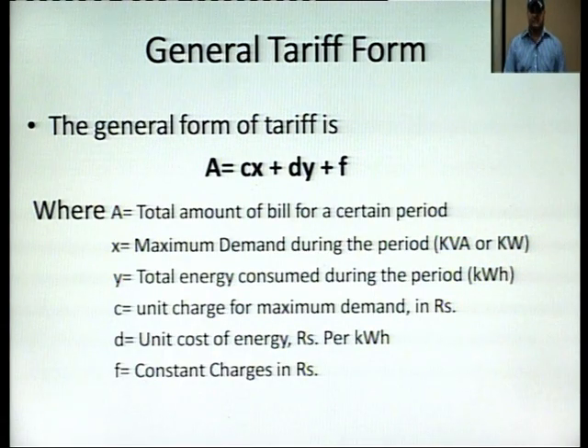Y is the total energy consumed during the period, in kilowatt hours. C is the unit charge for the maximum demand in rupees - so many rupees per kilowatt or per kVA. D is the unit cost of energy, in rupees per kilowatt hour - for example, nowadays rupees 6 per kilowatt hour. And F are the constant charges, also given in rupees.